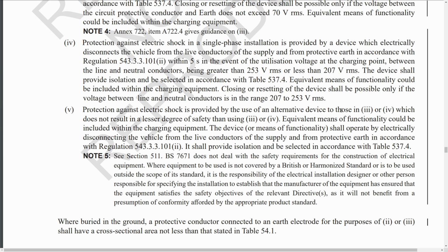So essentially this is some kind of device which monitors the voltage between the line and neutral conductors at all times. If it goes outside of this range, which is just your normal operating range for voltages, it will disconnect the conductors and the protective earth, and then it remains off until someone turns it on, and you won't be able to turn it on unless the voltage is within that normal operating range.